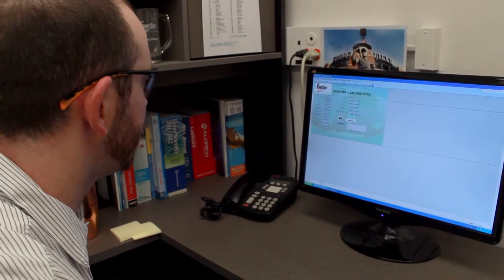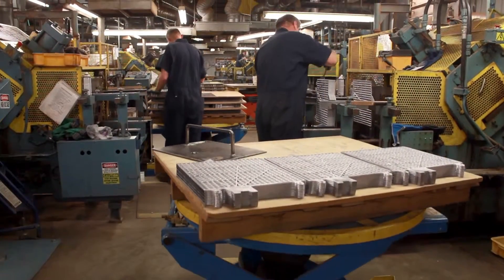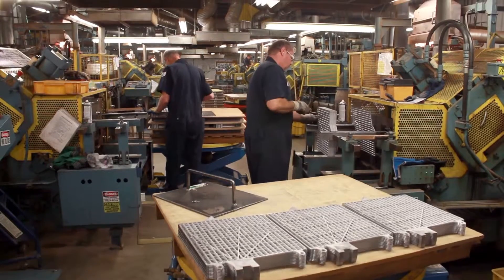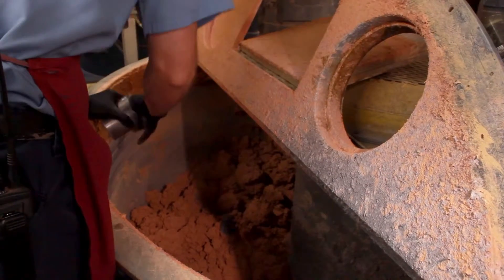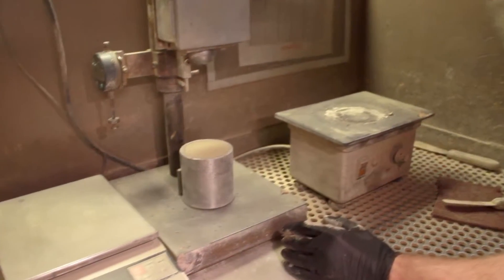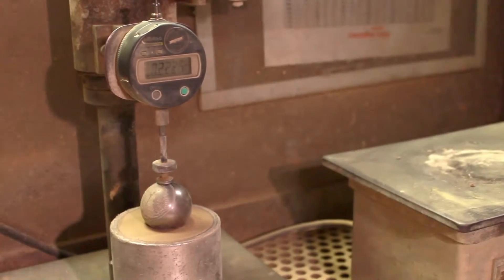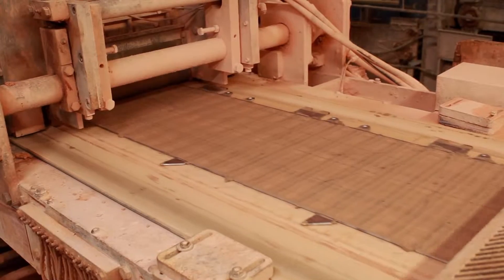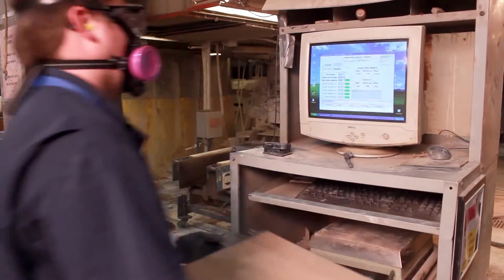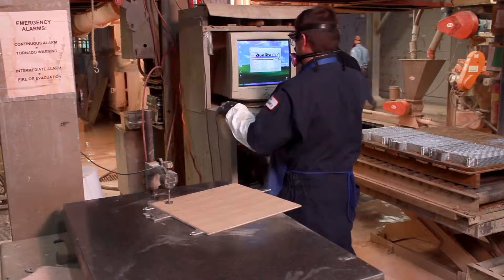Every sample lot is logged into the Comprehensive Materials Tracking System. This system allows traceability to materials used via individual cells' serial numbers. As the oxide paste is prepared, several quality checks are performed to ensure proper moisture content as well as chemical composition. The lead grid and paste are combined into a single monolithic unit or plate, with quality checks including plate weight, thickness and geometry performed to ensure the paste material completely fills all the voids in the plate.